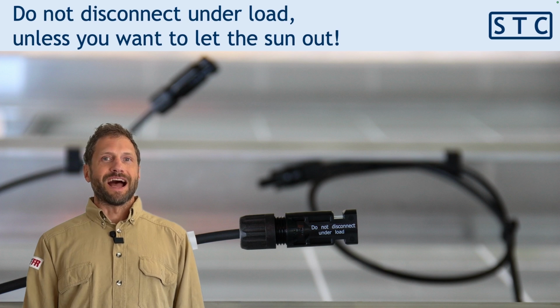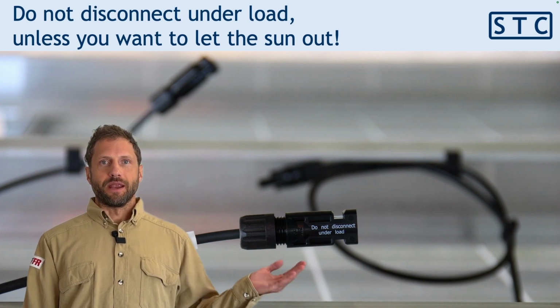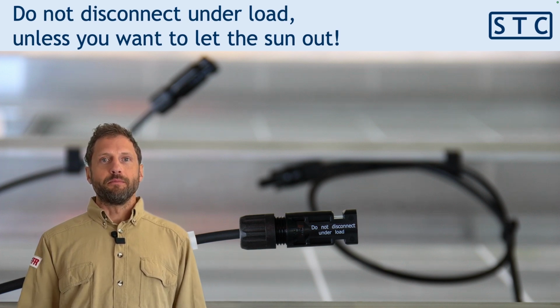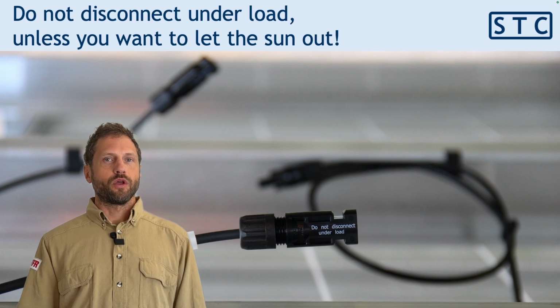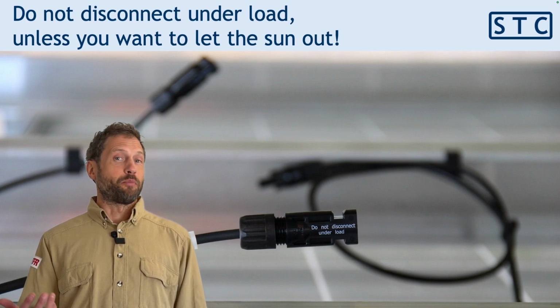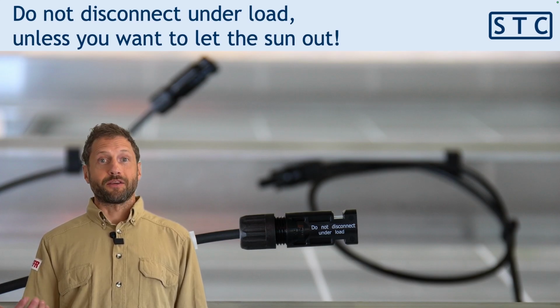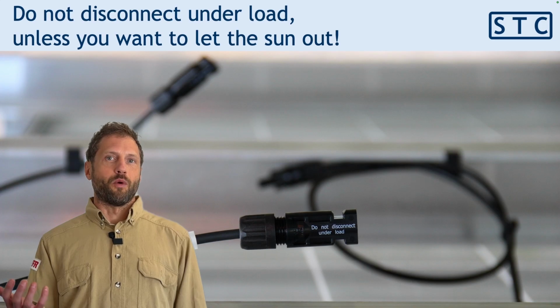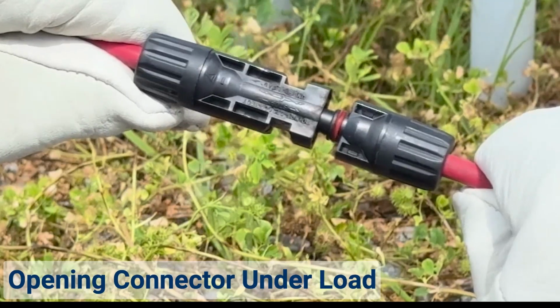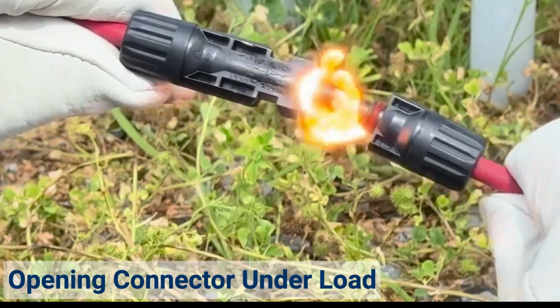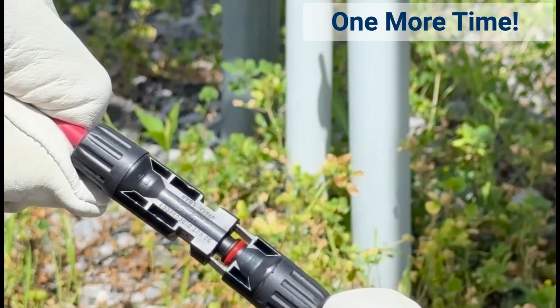If a device is non-load break rated, like this mating connector here, it's going to be marked "Do Not Disconnect Under Load" or something similar. And the purpose of that marking is to let us know that we shouldn't open it while there's current flowing unless we want to let the sun out. In case you were wondering, this is what that looks like. And once more for good measure.